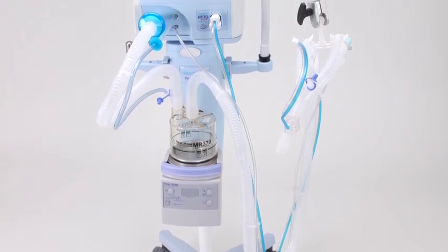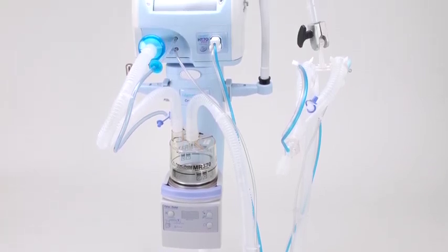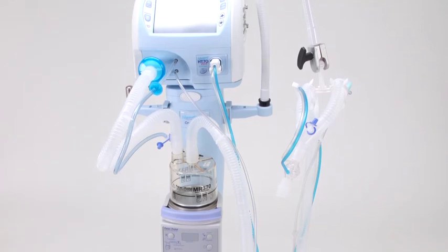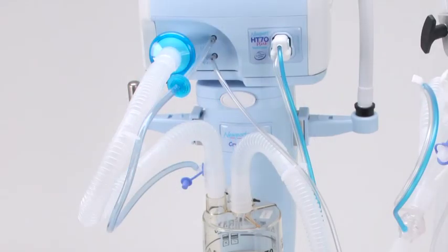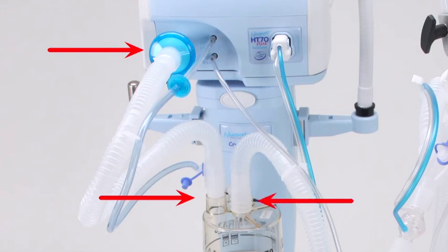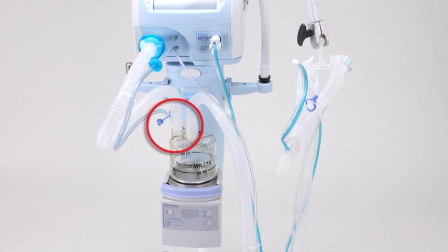short piece of tubing. This tubing is included in the package with the J-style circuit. Instead of connecting the main tubing directly to the ventilator, you will connect the short limb of the circuit tubing from the main flow outlet of the ventilator to the humidifier. Then connect the main part of the circuit to the outlet of the humidifier. Notice that I have connected the end that has the extra pressure port to the humidifier.